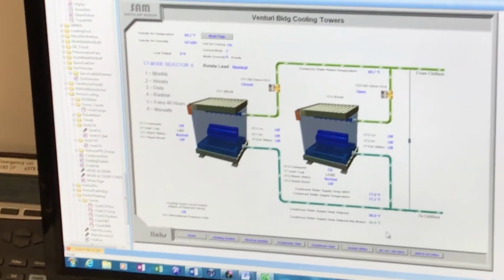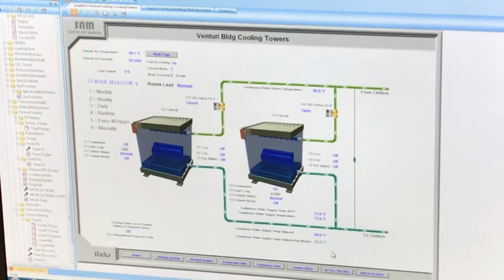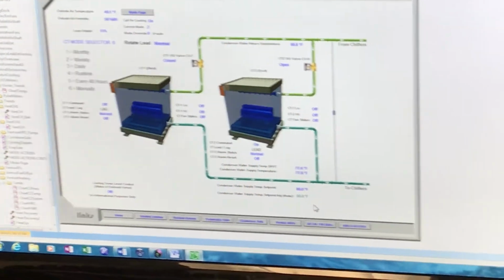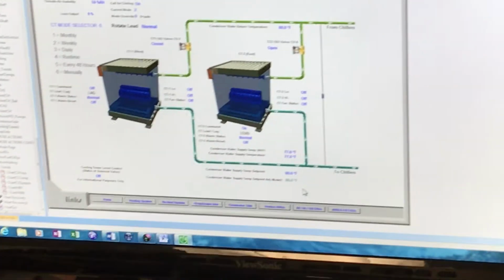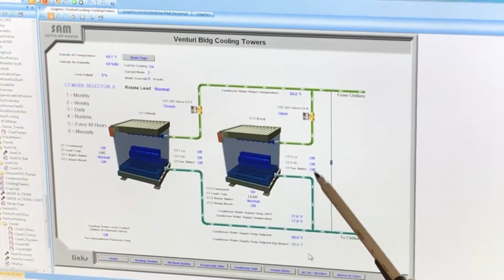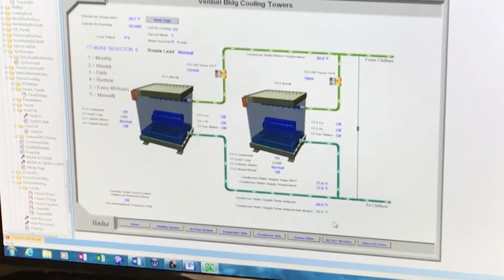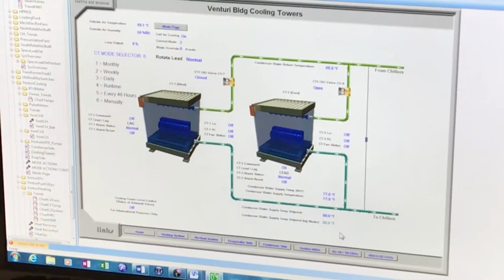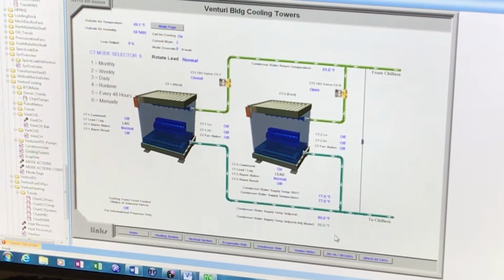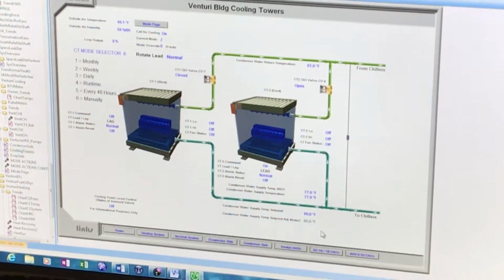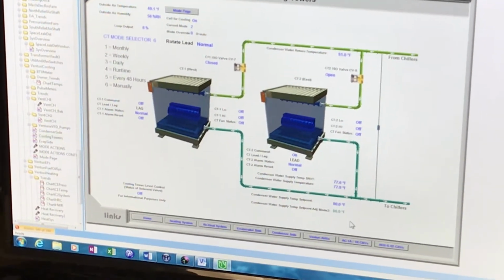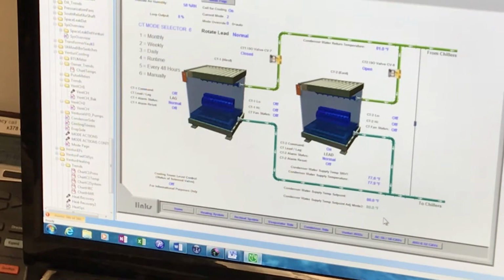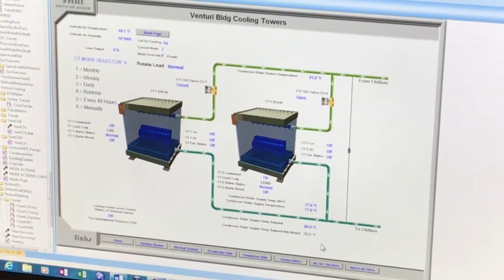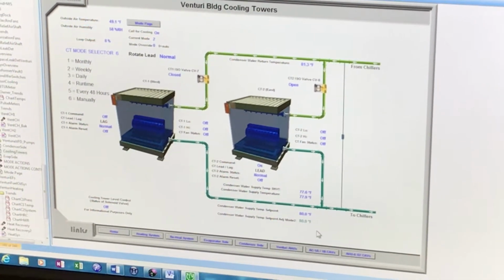Okay. So at 8%, it's still being called a little bit to be on, but not enough maybe to turn on. Maybe if over 10, it can turn on? I think it's 20. In general it's set so that 20 is the low stage, then 40 the second low, then 60 the third low, and then 80. So it's 20, 40, 60, 80, with a 10% differential. Yeah, that's what I remember. So that's what that loop means.